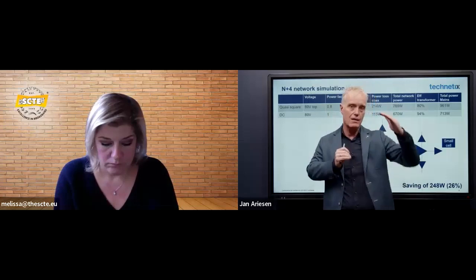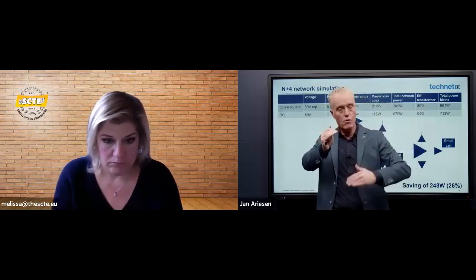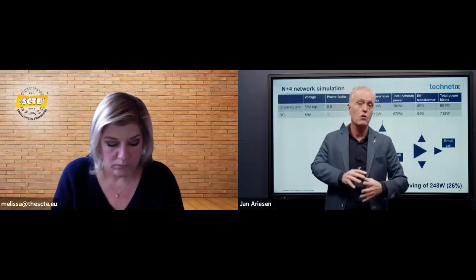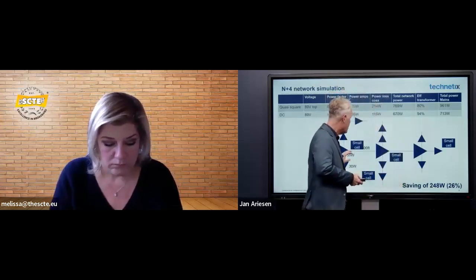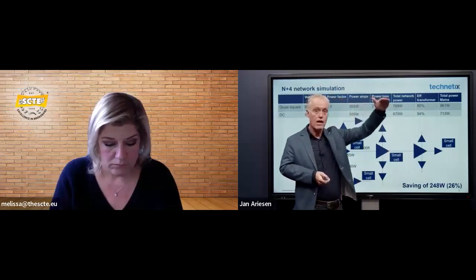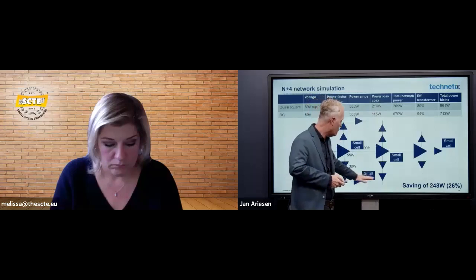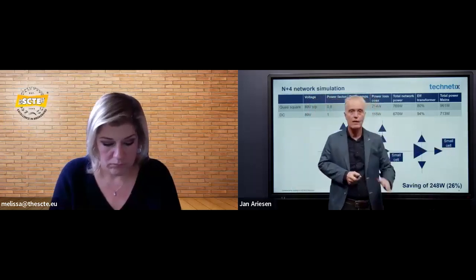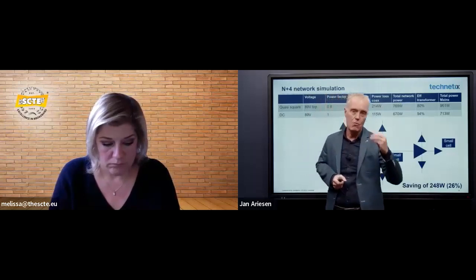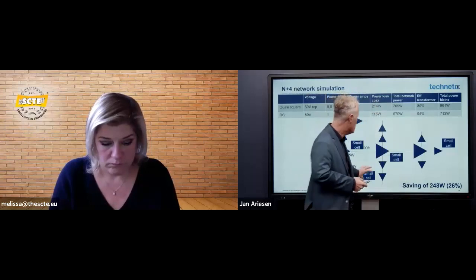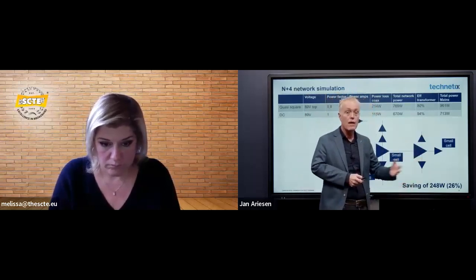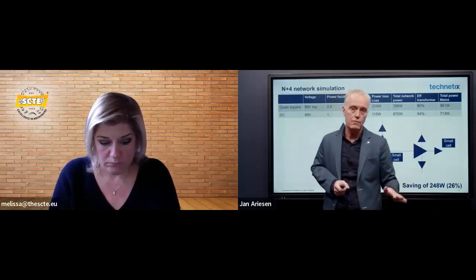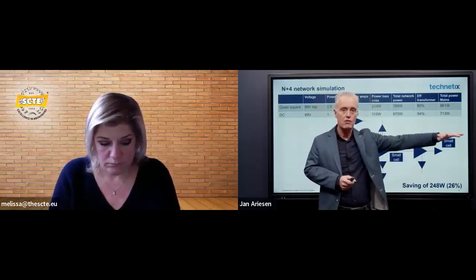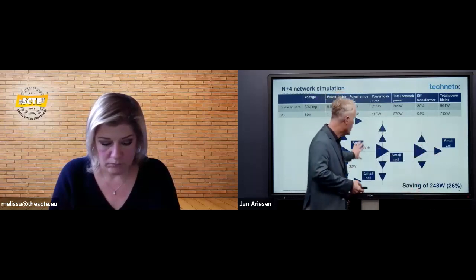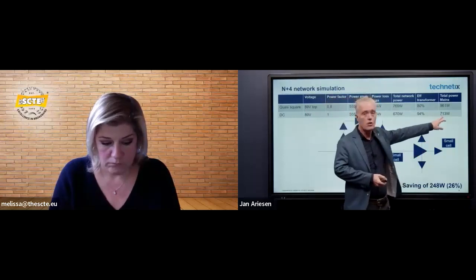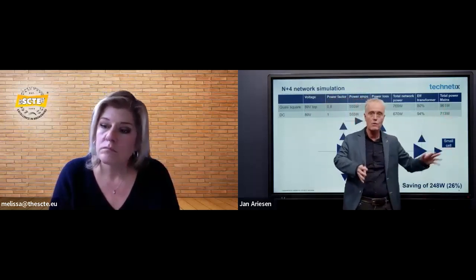It's very clear that the higher the current I have in the network, the lower the voltage will be, and my power consumption only goes up a lot. But with DC, my voltage stays much higher because I don't have that high current anymore, so the voltage is higher everywhere, the current is lower, and I can add more components to a network. Those components can be fed out of a network where quasi-square or sine wave couldn't do it. Just because the current is lower, we can go deeper in the network and have more power to give. Adding components will still raise this number since they draw power from it.